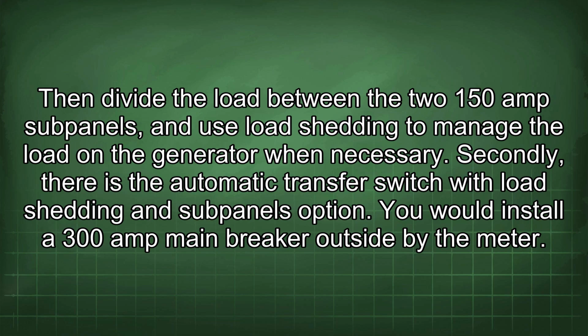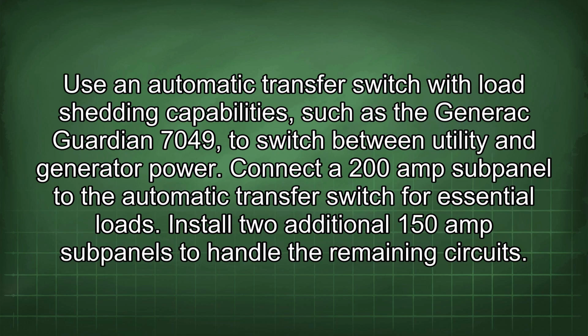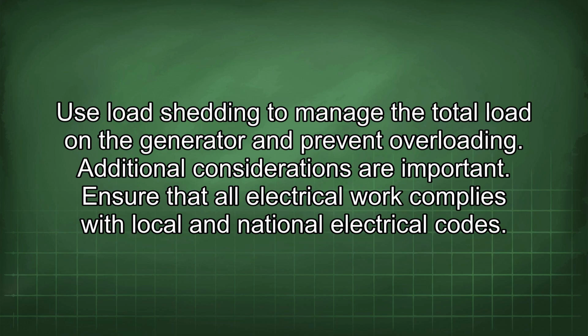You would install a 300 amp main breaker outside by the meter. Use an automatic transfer switch with load shedding capabilities, such as the Generac Guardian 7049, to switch between utility and generator power. Connect a 200 amp subpanel to the automatic transfer switch for essential loads. Install 2 additional 150 amp subpanels to handle the remaining circuits. Use load shedding to manage the total load on the generator and prevent overloading.